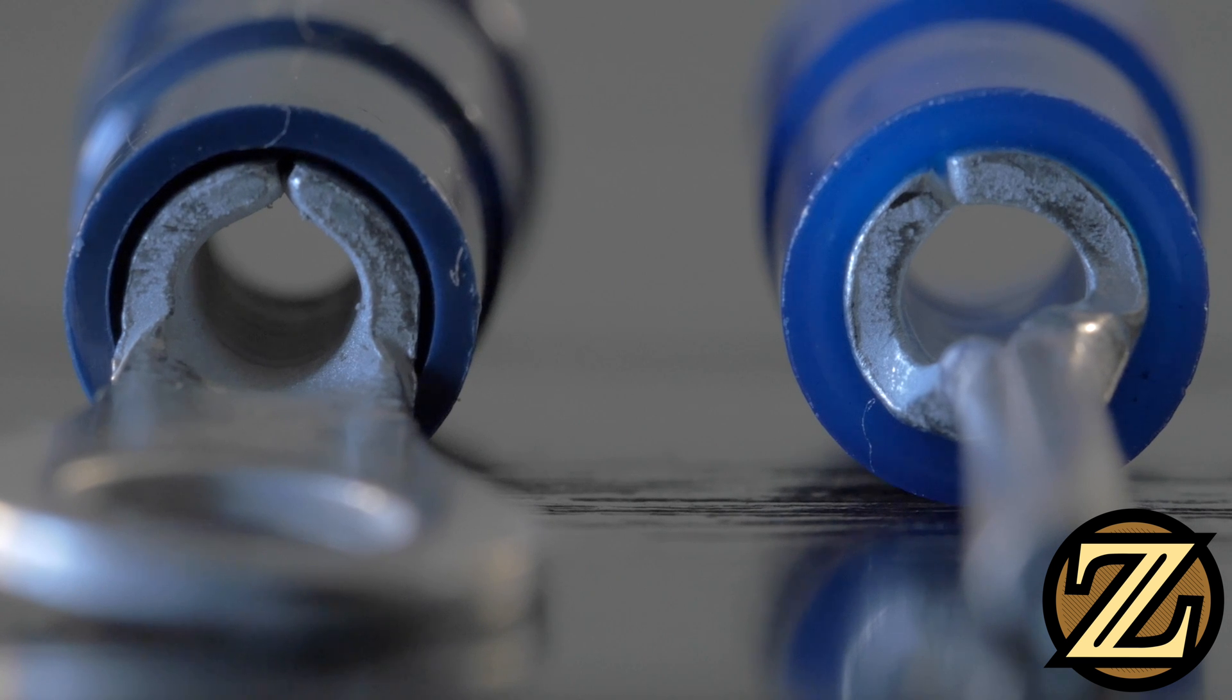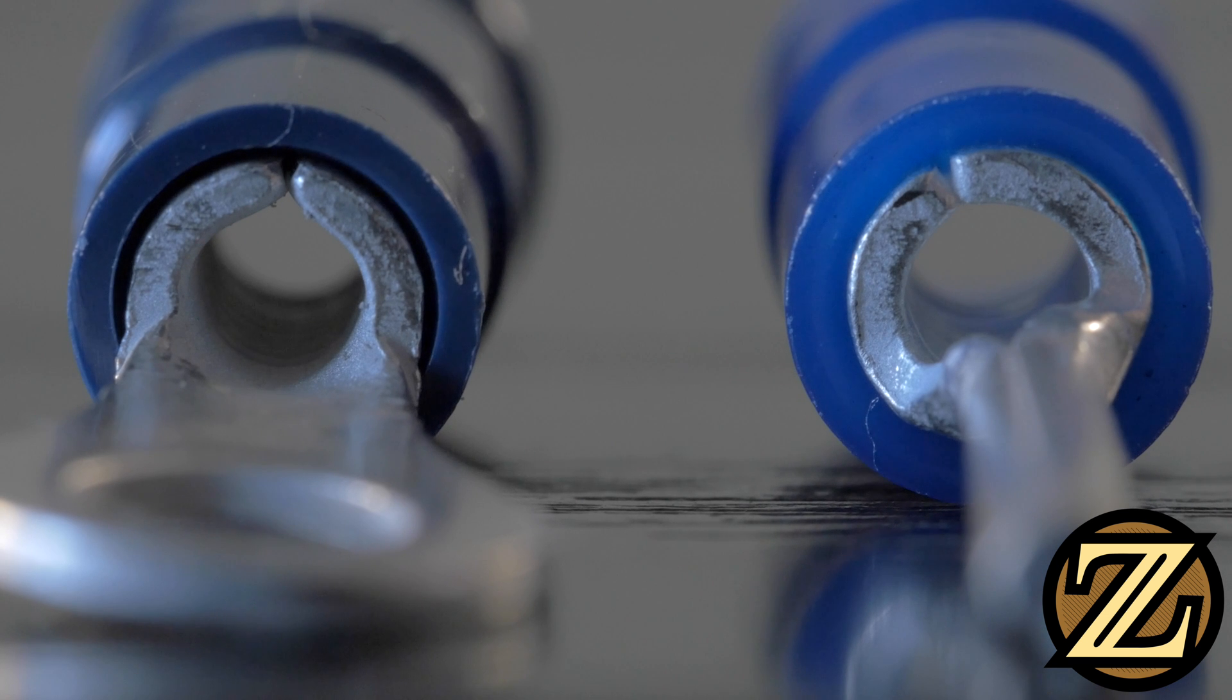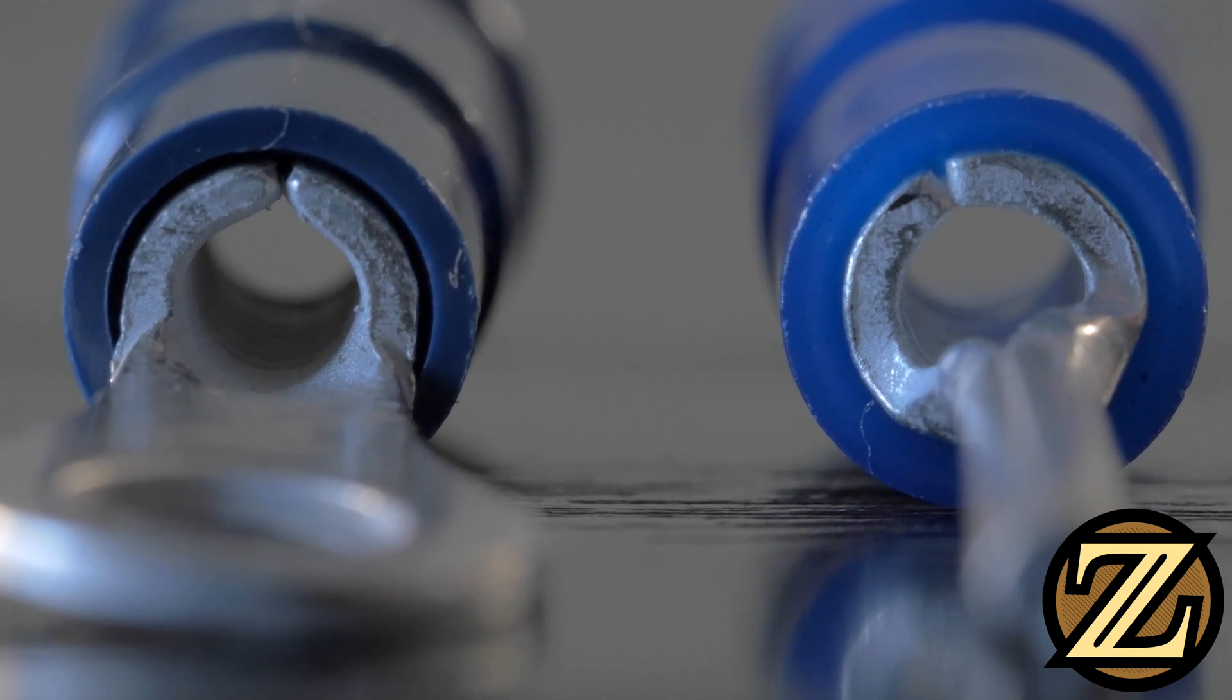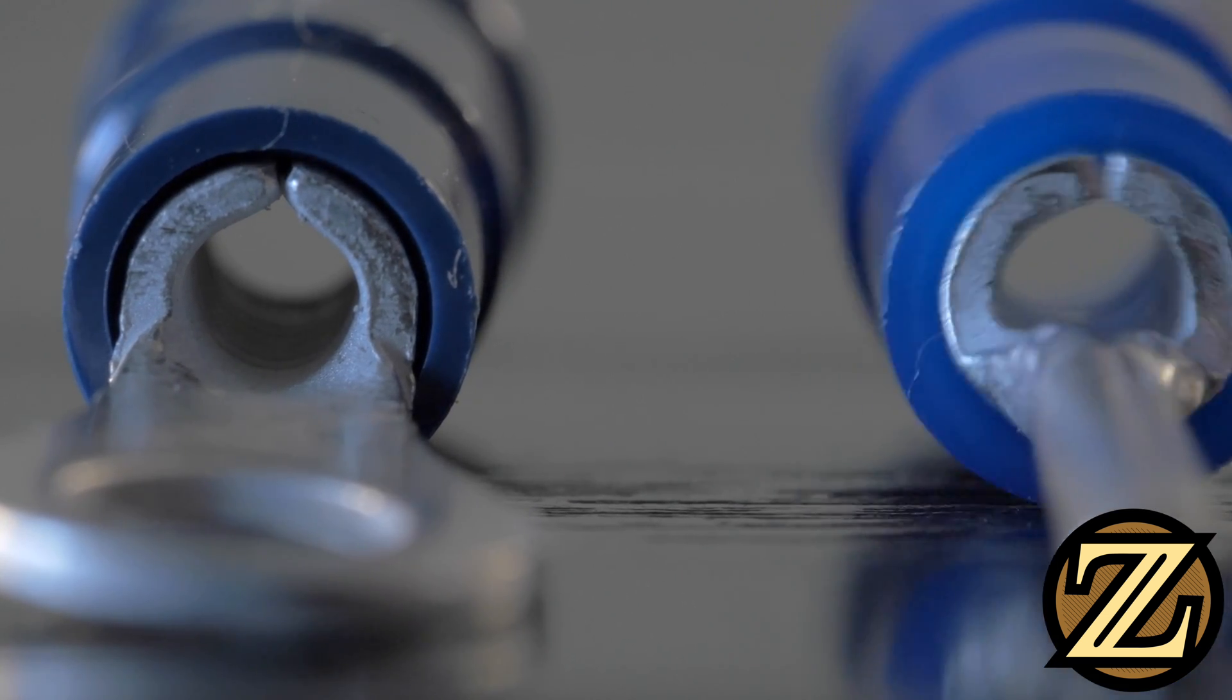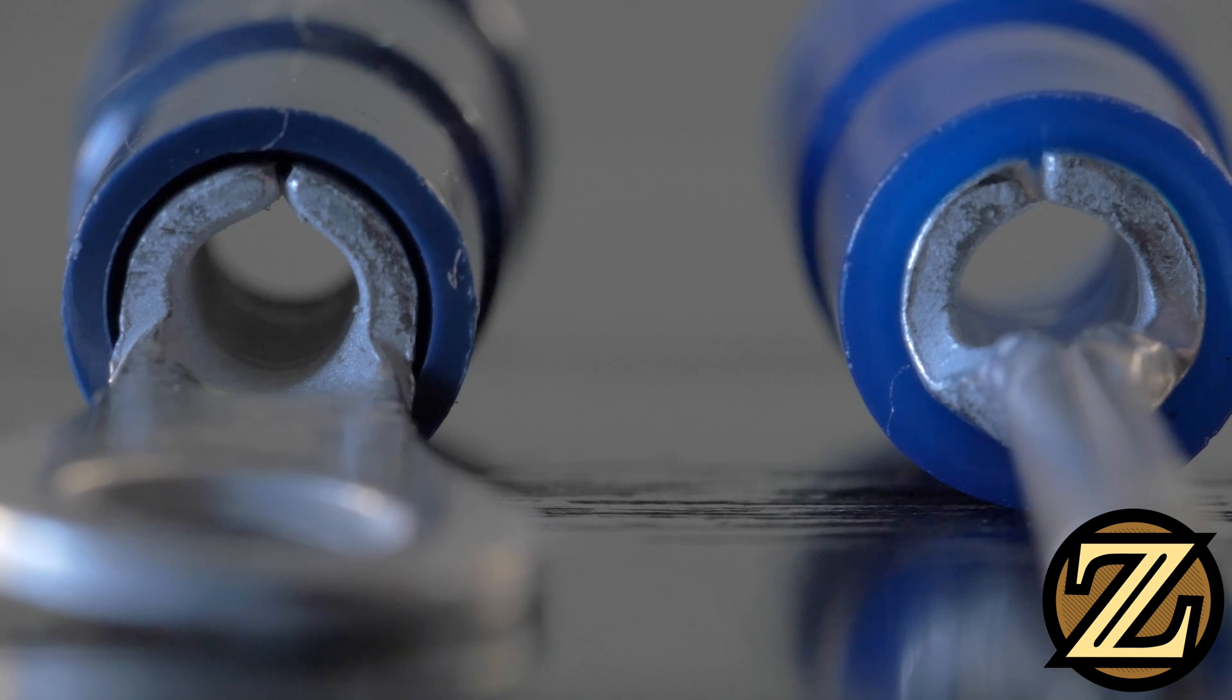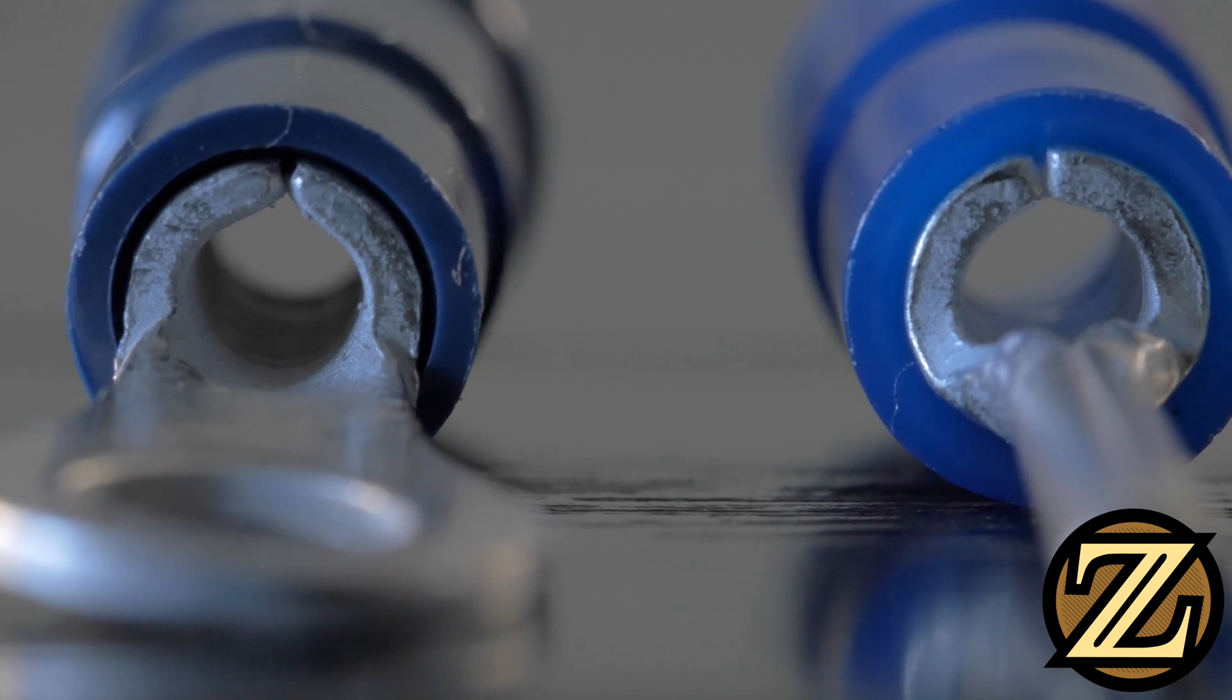Before you start, take a look at your terminal. You will notice a slit in the metal. Here you can see it at the top of the ring terminal and the pin terminal. The concept behind crimping is that we will deform the terminal and crush the wire in the process. The slit here allows the left and right side of the terminal to fold down onto the wire and create the cold weld.